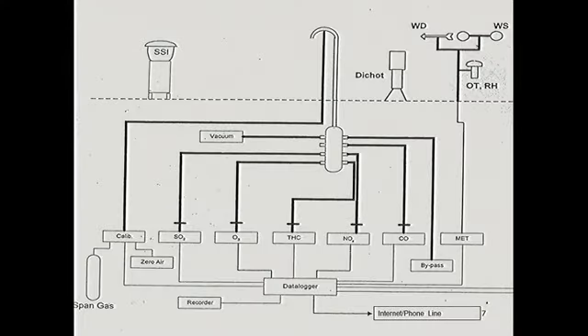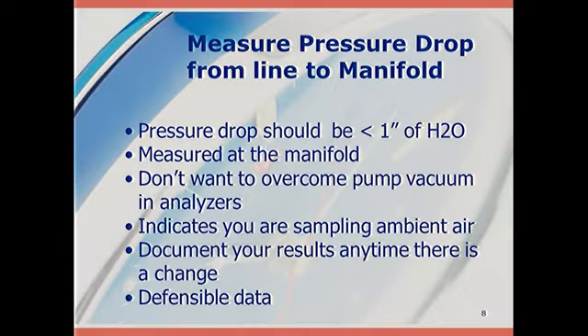Here's your typical air monitoring site. You've seen this picture already today. One thing that I don't see a lot, I see a lot of these at ARB sites, and some of these are even being taken away, is how to measure the pressure drop. And why is that important? It's important because we want to make sure that if you have a kicker pump or a booster pump on your probe, we don't want you to overcome your instrument pump pressure. So again, we're going to document that, and we're going to make that defensible.